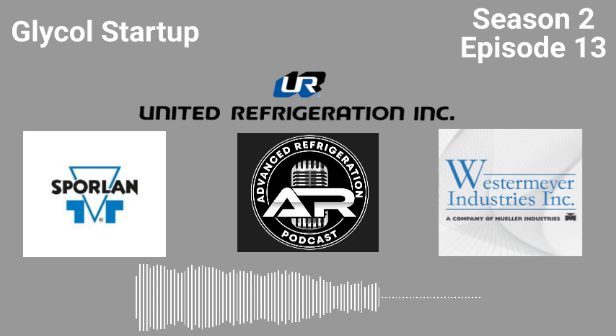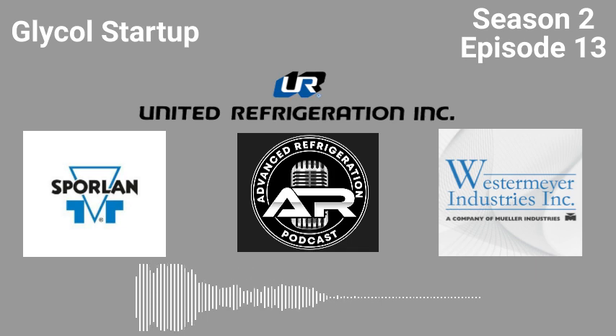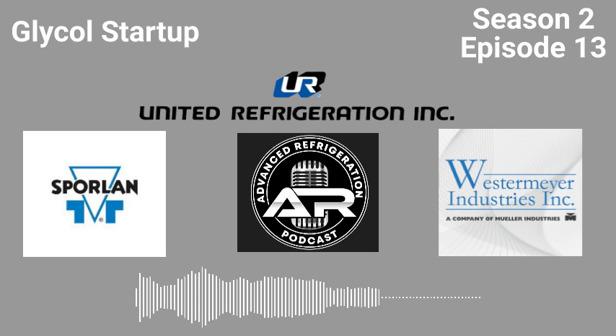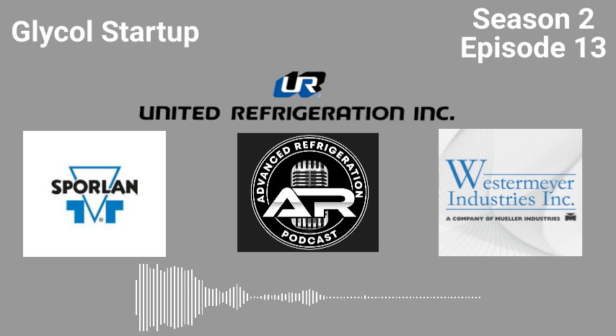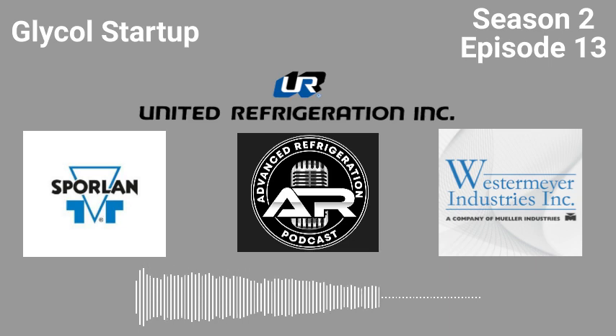So that's why, with circuit setters, it's imperative to get them set, and you want to have a VFD on the pumps. Unless you've got the poor man's VFD with the supply to return bypass. Not a big fan of that setup, but you need some way to maintain the pump pressures and the return flow. Walmart didn't use any VFDs. They were just using end of line. They have end of line circuit setters that are set at a minimum GPM. But at Walmart, you shouldn't have more than like 2 cases shutting off at a time.